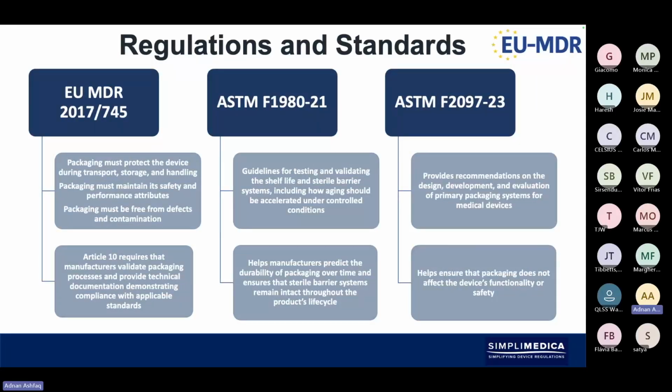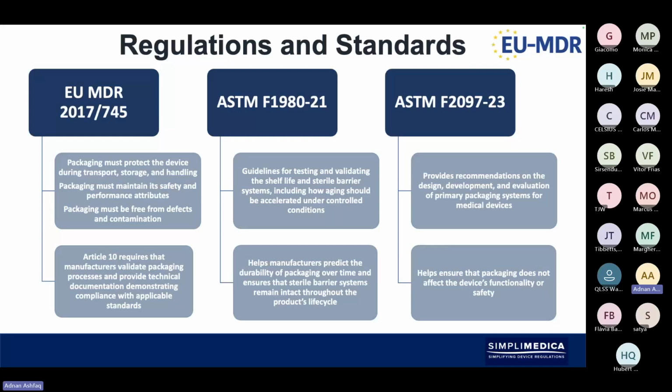Then the EU equivalent of the FDA, the European Medical Device Regulations, also looks at and defines in Article 10 that the manufacturer's responsibility is to validate packaging processes and provide technical documentation demonstrating compliance with applicable standards. And then, of course, it's similar again, where its aims and objectives are to ensure that the packaging is protecting the device throughout these different phases of transport, storage, and handling.